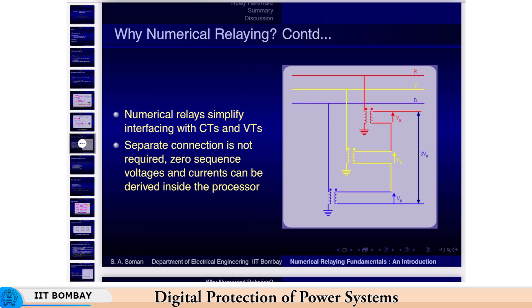Just to conclude about numerical relaying, they are the best compromise between economy and performance. Now, silicon devices are very cheap nowadays. Of course, there is a cost of the proprietary algorithms, etc. that goes into the relay, but if you were to manufacture a fresh numerical relay versus an electromechanical relay, the electromechanical relay would turn out to be costlier than the numerical relay.